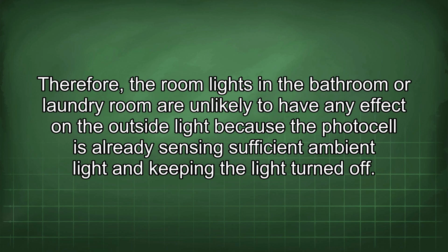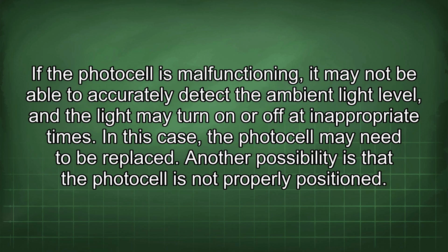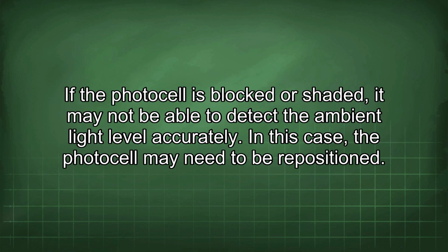Therefore, the room lights in the bathroom or laundry room are unlikely to have any effect on the outside light because the photocell is already sensing sufficient ambient light and keeping the light turned off. If the photocell is malfunctioning, it may not be able to accurately detect the ambient light level, and the light may turn on or off at inappropriate times. In this case, the photocell may need to be replaced. Another possibility is that the photocell is not properly positioned. If the photocell is blocked or shaded, it may not be able to detect the ambient light level accurately. In this case, the photocell may need to be repositioned.